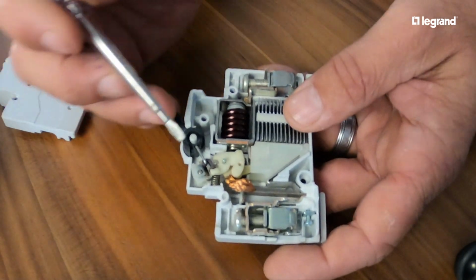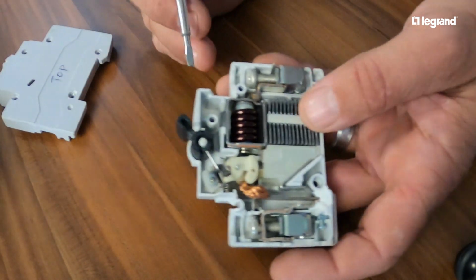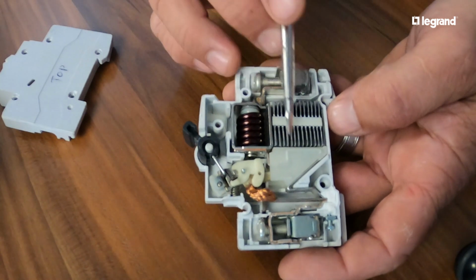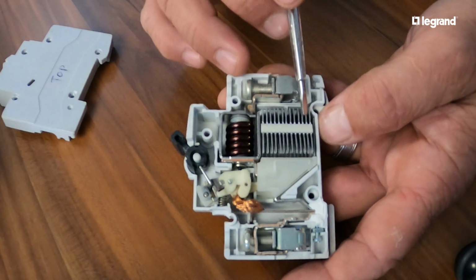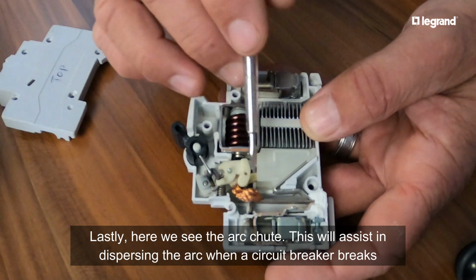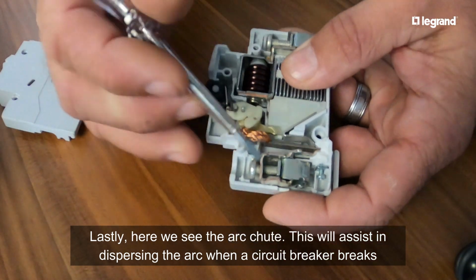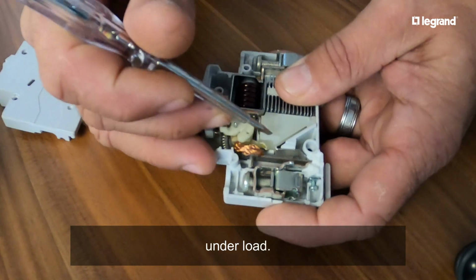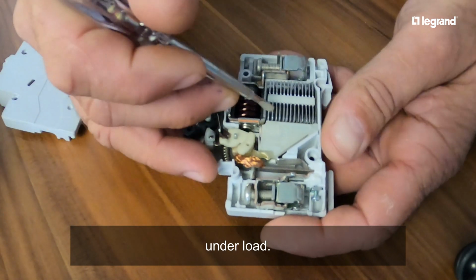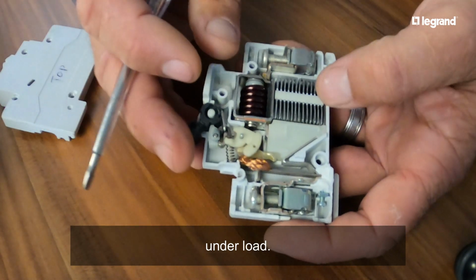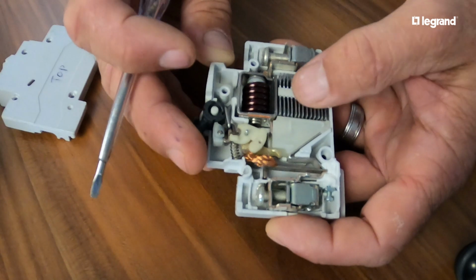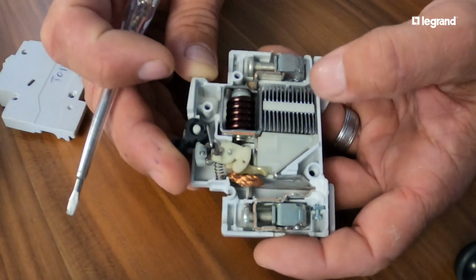So I'm going to illustrate now, for example, a short circuit. And lastly, we've got the arc chute here. This arc chute breaks the arc. If you look at the contact there at the bottom, once that contact breaks, there's an arc that develops, and these little fins help disperse the heat so you don't have too much heat in one point.